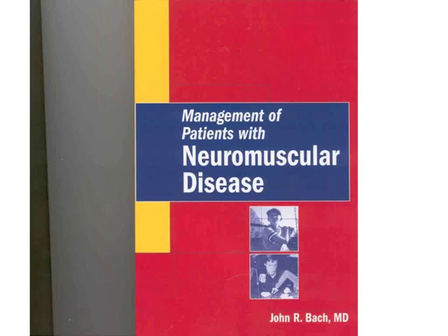If you set a volume on a volume cycled machine, let's say you set it to 1 liter, the machine delivers a liter of air and you hold that, but that liter of air creates a pressure in the lung, maybe 20 centimeters of water. Now it's set to give you another liter of air. Well, the machine doesn't care what the pressure is because it's not a pressure setting. It's set by volume. So it gives you another liter. Now you've got 2 liters, and it'll give you a third liter. It's only limited by the high pressure limit that you set on the machine, which can be 70 centimeters of water or more.